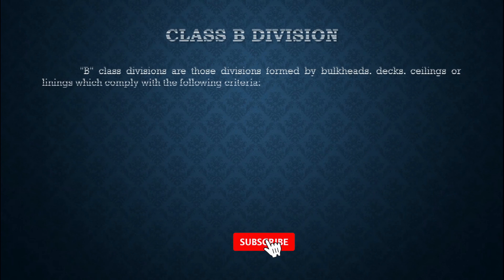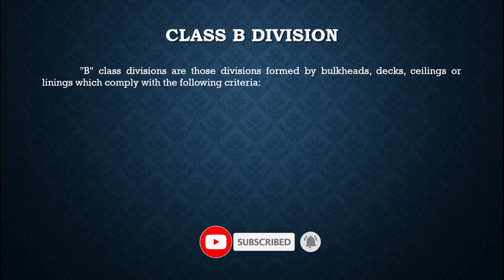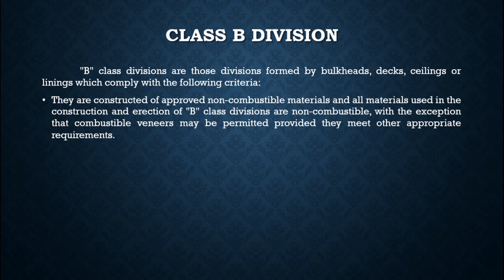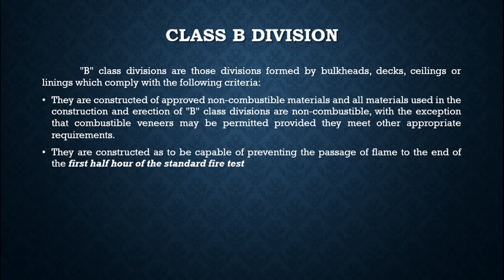Class B divisions are those formed by bulkheads, decks, ceilings, or linings which comply with the following criteria: they are constructed of approved non-combustible material, and all materials used in the construction and erection of Class B divisions are non-combustible, with the exception that combustible veneers may be permitted provided they meet other appropriate requirements. They are constructed so as to be capable of preventing the passage of flame to the end of the first half hour of the standard fire test — compared to one hour for Class A divisions.